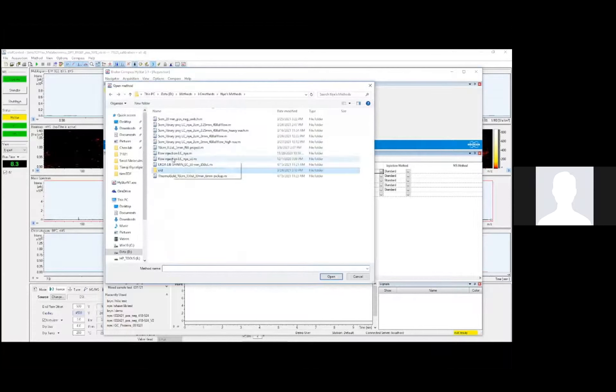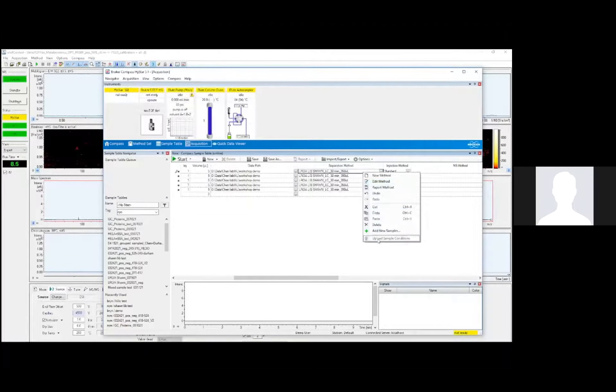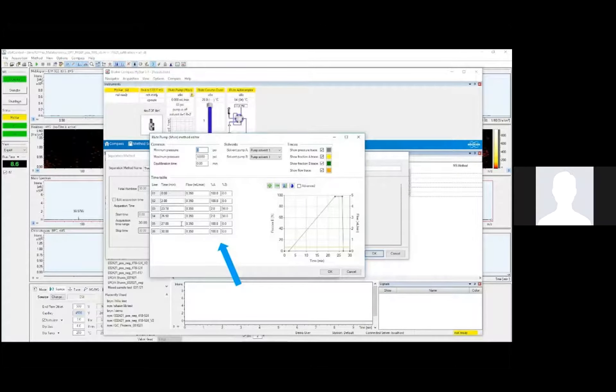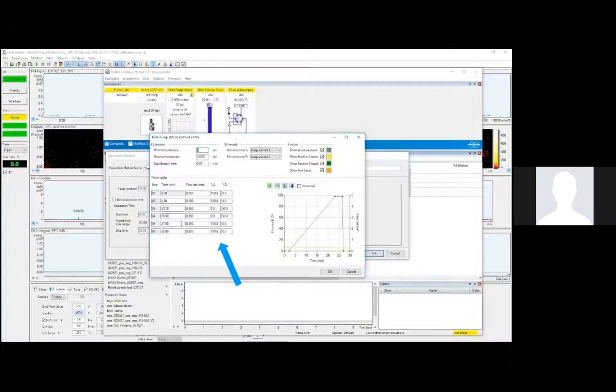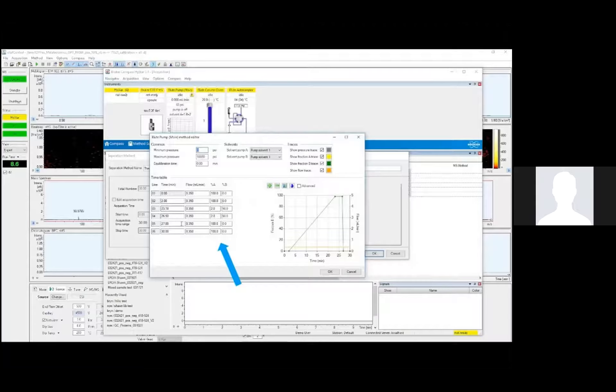And now I need to choose an appropriate LC method. Okay, so I've opened the LC method, and now I'm opening the elute pump settings. On the bottom left side of the pump settings, you can see the timetable. Each point on the table has a corresponding time at which you can apply a different flow rate, or a different percent A and percent B. We don't change the flow rate here, but we do vary the percent A and B. You can see the visualization of the gradient we set up using the graph on the right. And it is this gradient on our reverse phase column that pushes the more hydrophobic compounds off the column as peaks.